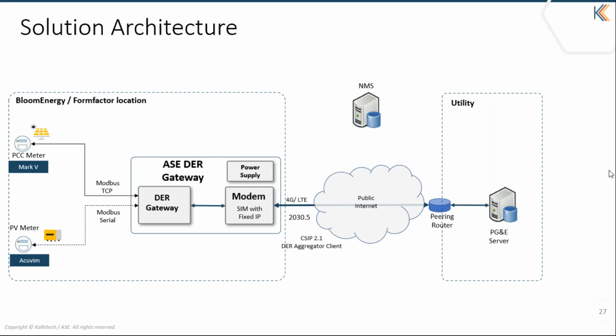So in summary, downstream we are collecting data through Modbus TCP and Modbus serial, and to the utility side, the PG&E side, we are pushing data through the 2030.5 protocol. That's the high-level summary of this data transaction. And here we are using the aggregator client capability of the DER Gateway. As Nirmal mentioned earlier, the DER Gateway can be configured as a direct client or aggregator client. Since we had 2 meters downstream, we used the aggregator client capability and that configuration mode to get the data into the utility data center.